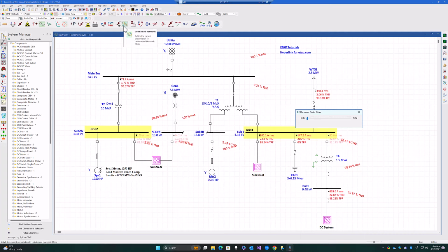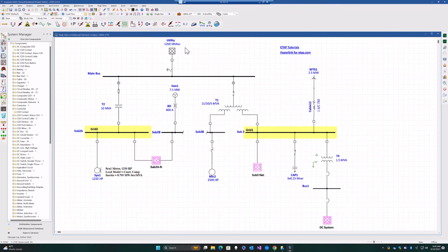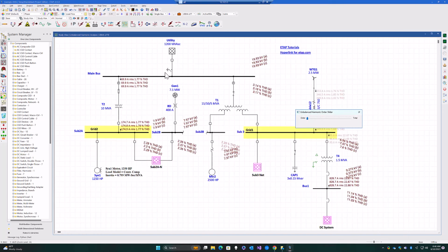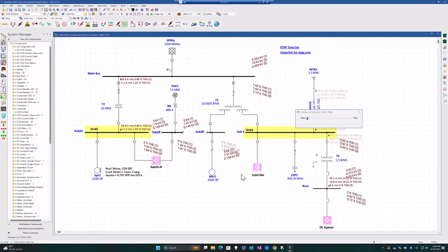But for unbalanced harmonics, we've added a brand new mode into ETAP that uses unbalanced load flow as a fundamental enabler for the unbalanced harmonic simulation. When you run the harmonic load flow, as expected, we display the phase A, phase B, and phase C voltages, as well as the voltage and total harmonic distortions. You can also switch between all phases and all sequences, so you can see the sequence values in terms of positive, negative, and zero sequence as well, including the THDs for voltage as well as current.